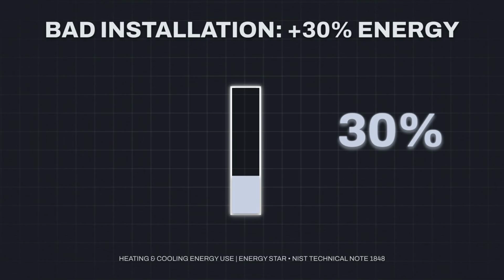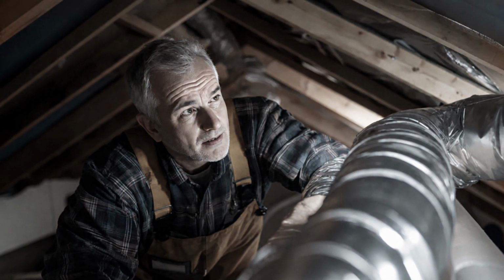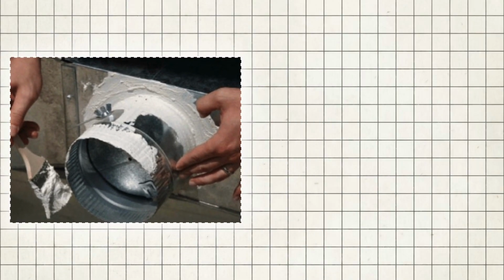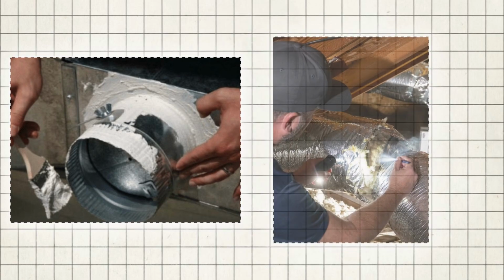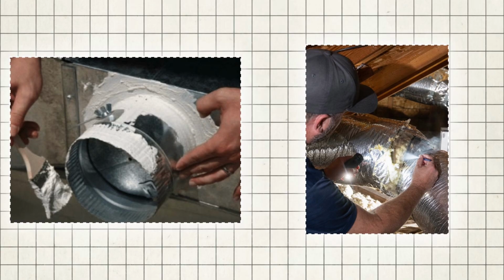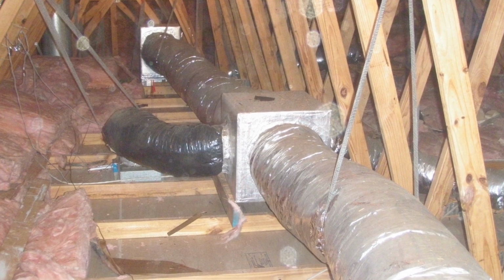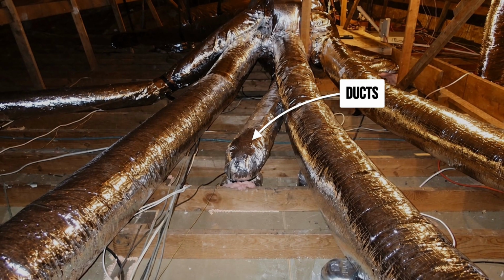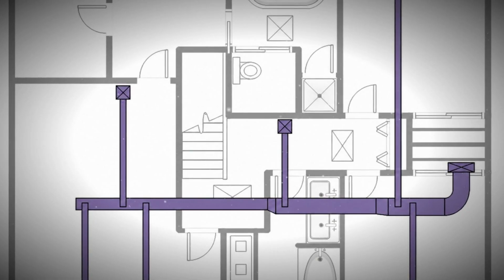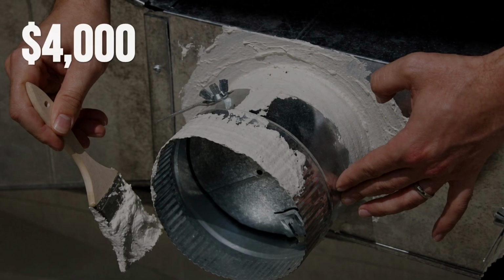30%. Run the math. A $15,000 variable speed system on ducts leaking 25%. Against an $8,000 two-stage on ducts that got sealed first. The cheap one wins. It isn't close. That's the reframe. Level 7 was never the top. Your ducts are the ceiling over all of it, and every level above 3 sits under it. Duct sealing runs $500 to $4,000. It's the best returning line item nobody puts on a quote.